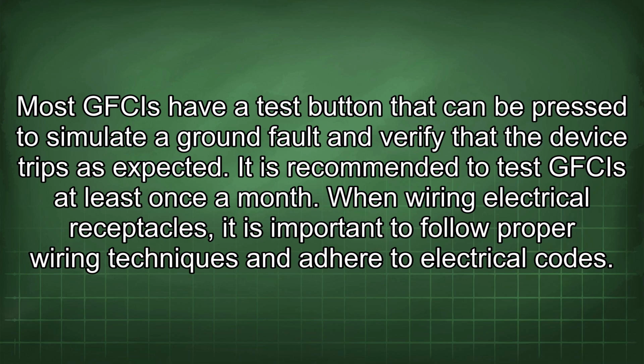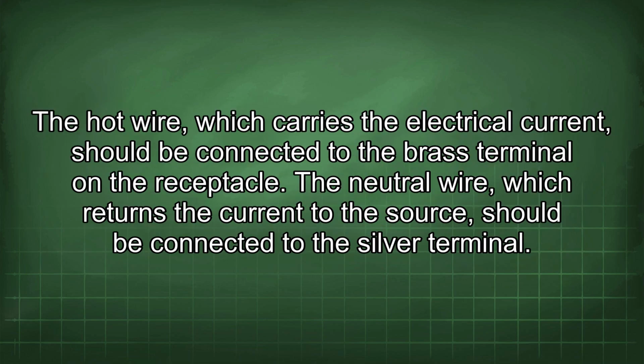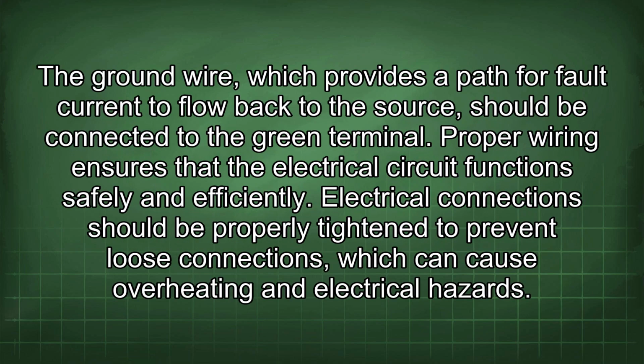When wiring electrical receptacles, it is important to follow proper wiring techniques and adhere to electrical codes. The hot wire, which carries the electrical current, should be connected to the brass terminal in the receptacle. The neutral wire, which returns the current to the source, should be connected to the silver terminal. The ground wire, which provides a path for fault current to flow back to the source, should be connected to the green terminal. Proper wiring ensures that the electrical circuit functions safely and efficiently.